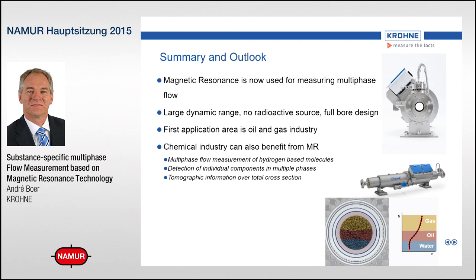Looking to the future: magnetic resonance flow meters are being used for multiphase flow measurement right now. It can be done and we are seeing increasing demand. The meter has a large dynamic range and is a very elegant measurement principle — a single measurement to measure individual phases, no radioactive source necessary, and a full bore design. We've designed it first to be used in the oil and gas industry upstream, directly at the oil well, measuring oil, water, and natural gas mixtures — and that's what we are aiming at right now.